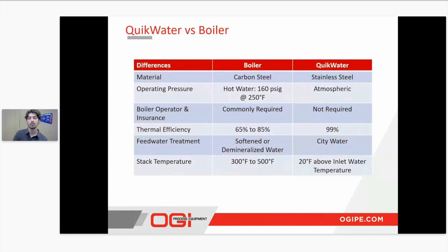So going over a couple of the key points I've gone over here for a QuikWater versus a boiler, and how it may play into how you want to approach a rental situation. Boilers are typically made out of carbon steel, whereas QuikWater is always manufactured with stainless steel. Operating pressures, as I mentioned, the QuikWater is always going to be an atmospheric vessel. You have no need for any ASME labels on there. You don't need the yearly shutdown and inspection as you would for a boiler in that regard.